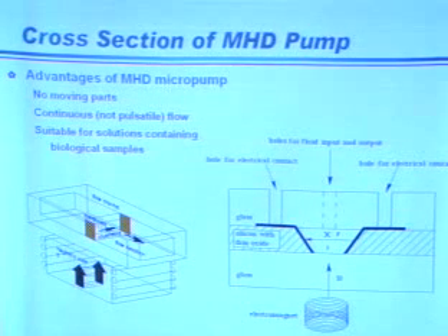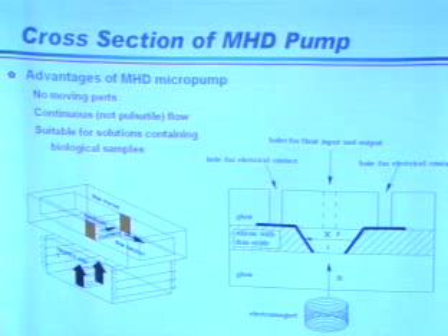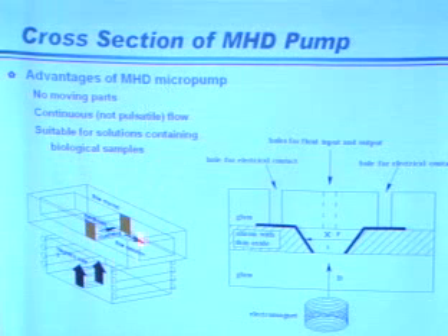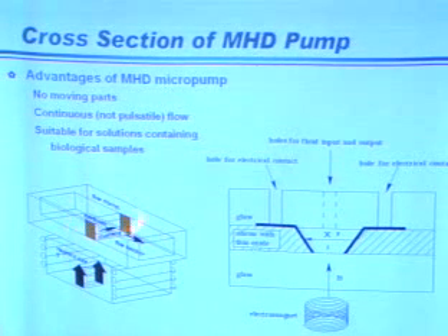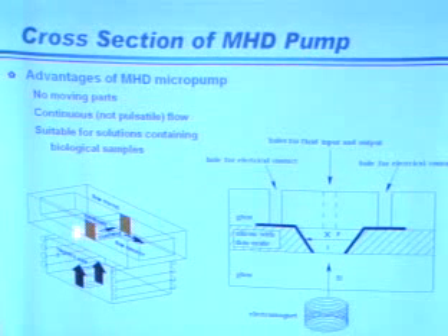And so the advantage, of course, is that you have no moving parts. There's no flapping membrane that needs to push it for a pulsatile flow. One limitation, obviously, is that you cannot do non-conducting fluids. But most biological samples have some charge in them, or you can have enough separation so that you can generate that force. And remember, the force is only generated in this electrode cross-section area. Once you're beyond that area, you start generating pressure-driven flow, which has some advantages.